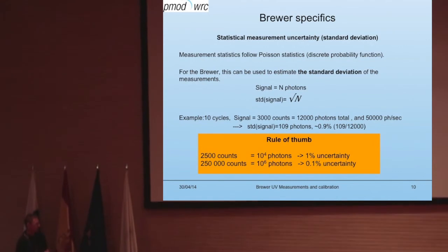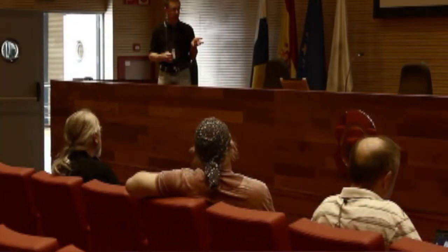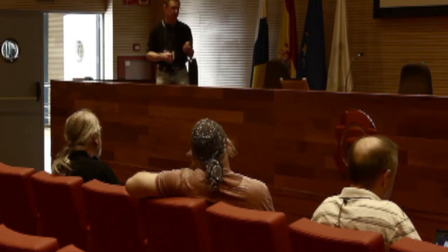For example, but this is also not operational. In my case, I always calibrate my instrument without any neutral density filter. And then I know the transmission of my neutral density filter because I have measured it with other methods. And then in my analysis, I will take the sensitivity, I will take my measurement that has been done with whatever neutral density filter I needed, and then in addition I will apply the known transmission of this neutral density filter, and this allows me to have a lamp calibration without neutral density filter to have high counts.